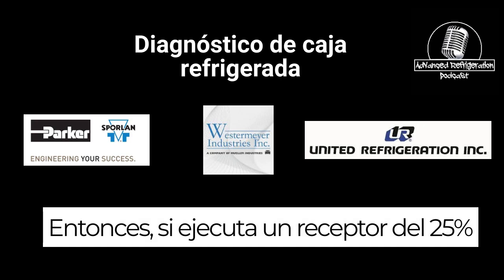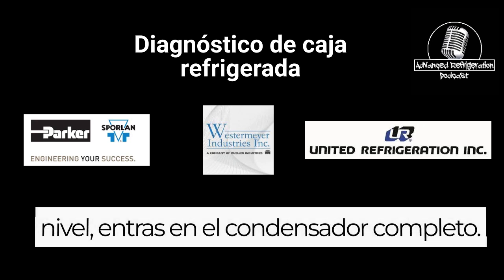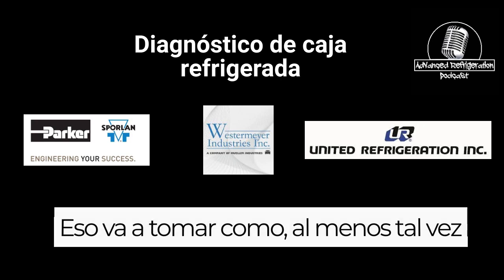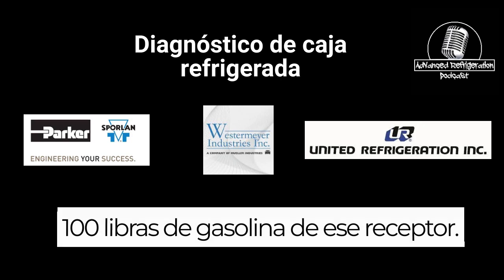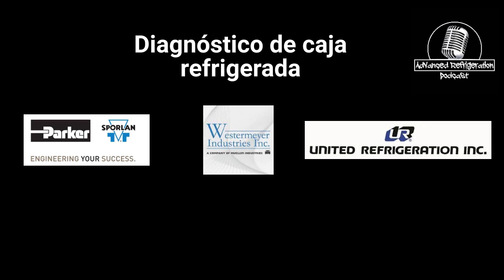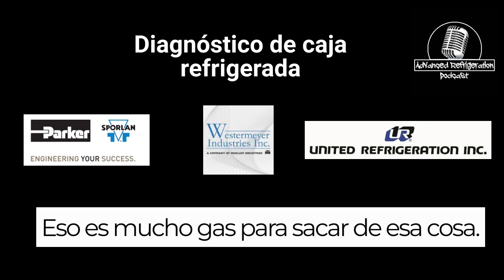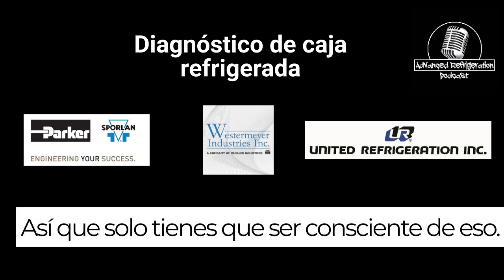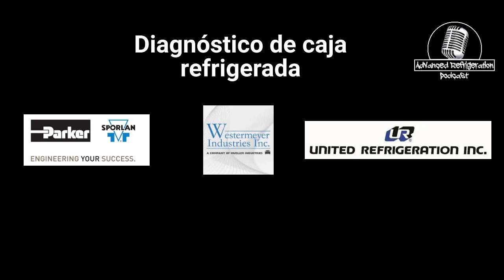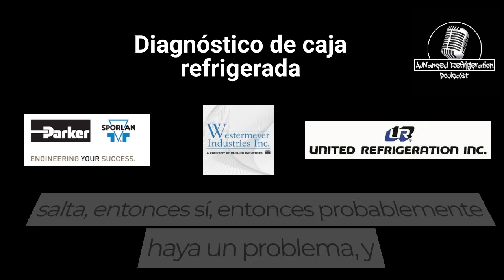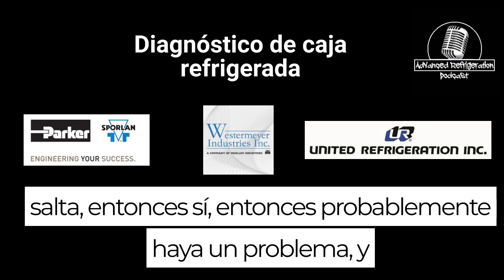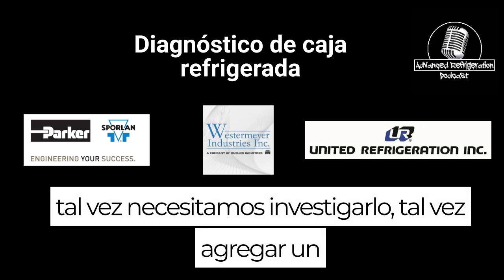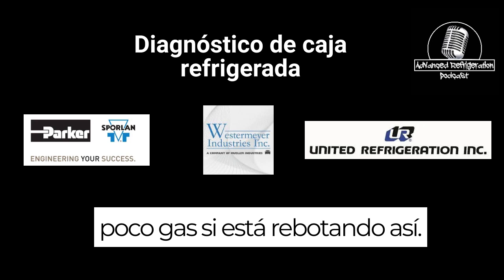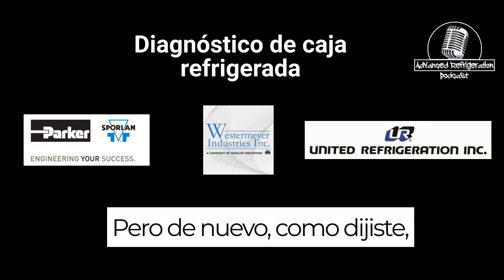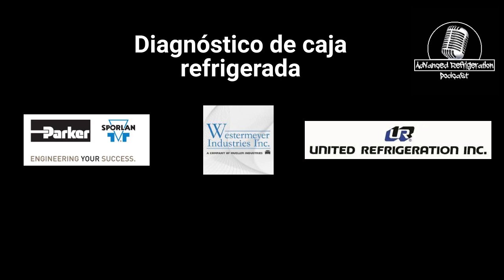So if you're running a 25% receiver level and you go into full condenser, that's going to take at least maybe 100 pounds of gas out of that receiver. That's a lot of gas to take out of that thing, so you just got to be mindful with that. I typically tend to graph it, and if I see it jumping, then there's probably an issue, and I need to look into it, maybe add a little gas if it's bouncing like that. But again, like you said, it all depends on customer spec.